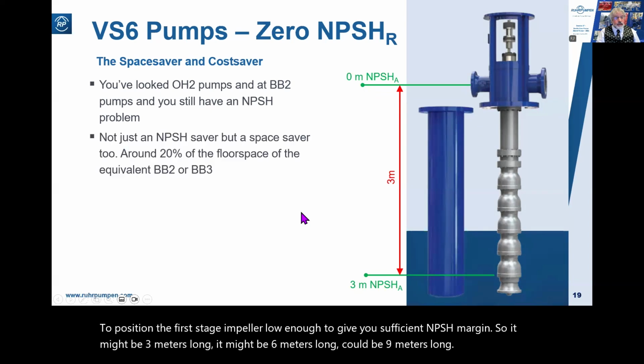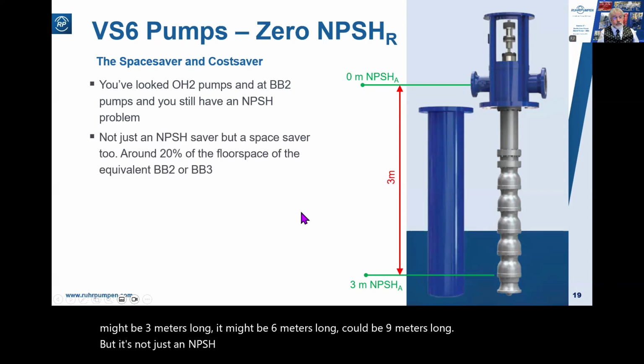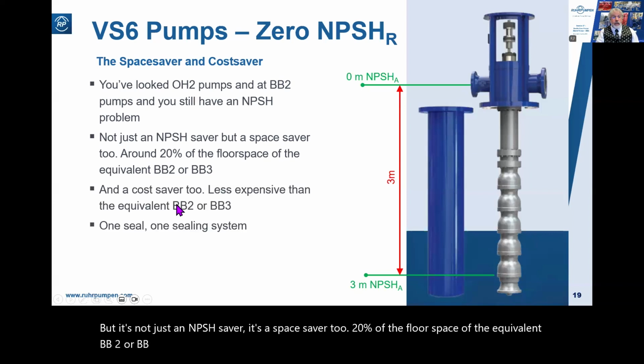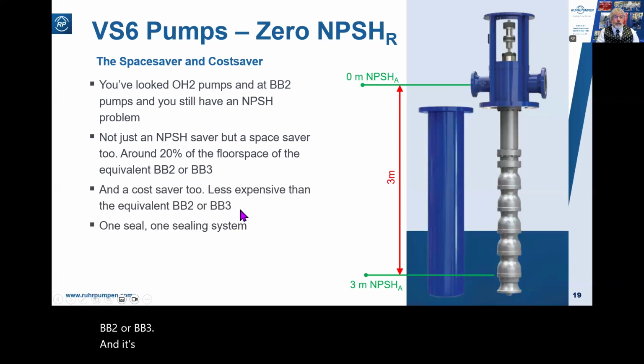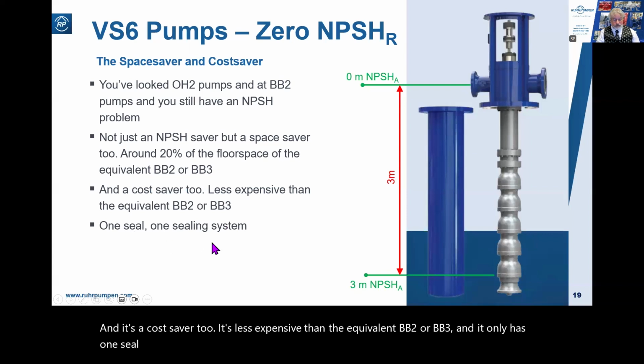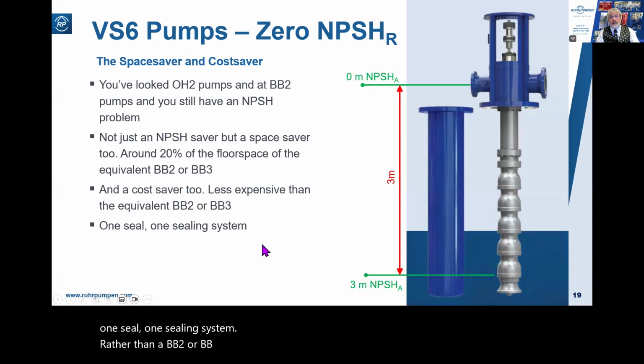But it's not just an NPSH saver, it's a space saver too. 20% of the floor space of the equivalent BB2 or BB3. And it's a cost saver too. It's less expensive than the equivalent BB2 or BB3, and it only has one seal, one sealing system, rather than a BB2 or BB3, which would of course have 2 seals and 2 sealing systems.